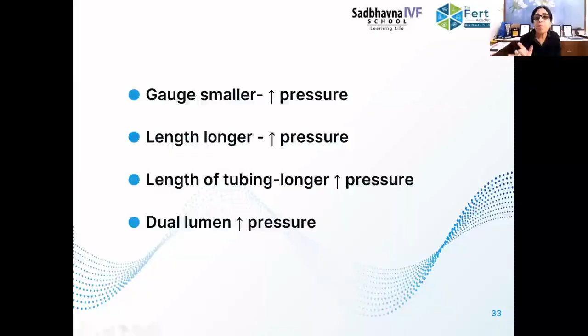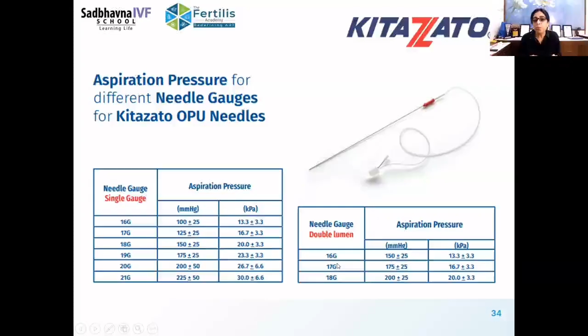Now, this is specifically mentioned only with Kitazato. Nowhere else are the pressures mentioned. So as you can see, in a 17 gauge needle, the aspiration pressure which they suggest is 125 plus or minus 25, that is 100 to 150. And when you use a 17 gauge double lumen needle, you can see that the recommended pressure is 50 mm of mercury more than for a single lumen. So that's how the physics is.